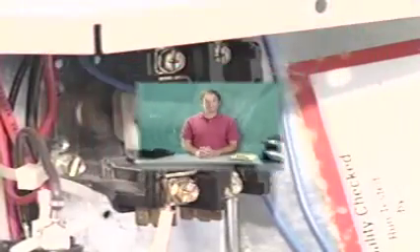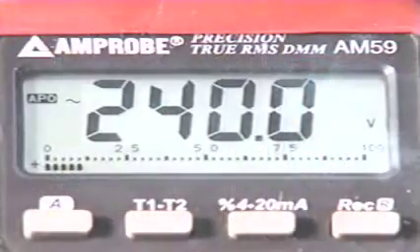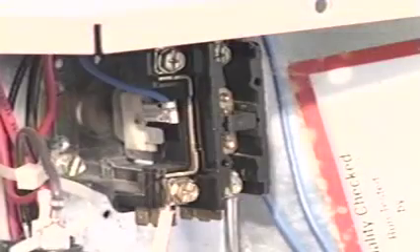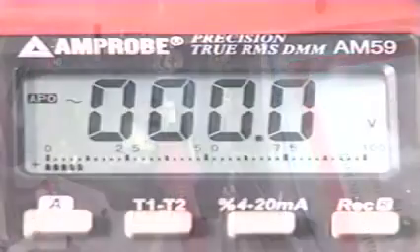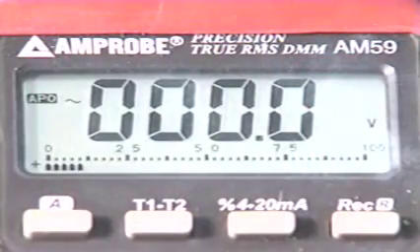The compressor failure could be due to an electrical or sealed system problem, so you'll need to check both areas to determine the cause of the problem. A voltage check at the contactor shows that the correct supply voltage is present. However, a low voltage check at the contactor terminals shows 0 voltage. This explains at least one reason why the compressor and condenser fan are not running.